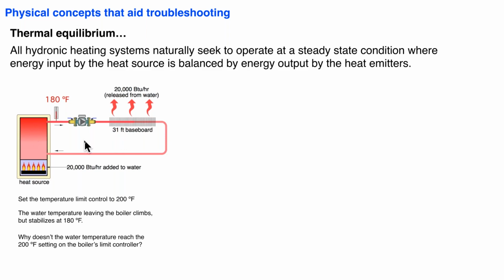And let's say we take all the controls off the system. We don't have a high limit control. We don't have anything that could potentially interrupt this natural process of the system finding an energy balance. Well, once that system stabilizes, it would stabilize at a supply temperature of about 180 degrees Fahrenheit. Even if we put a limit control back on the boiler and set it for 200 or even 220, the system isn't going to go above 180. It doesn't have to. At 180 degree supply temperature, this 31 feet of baseboard can dissipate 20,000 BTUs per hour, the same as what the heat source is putting in. So there's no reason for the system to go higher.